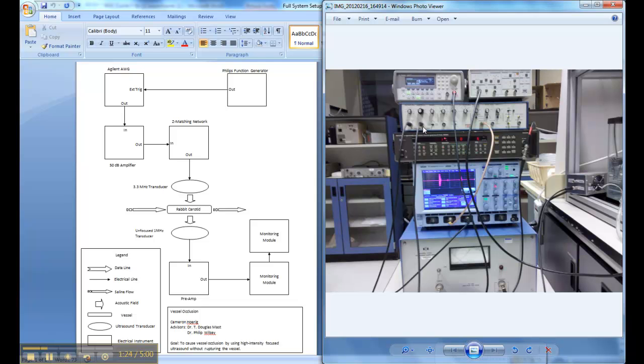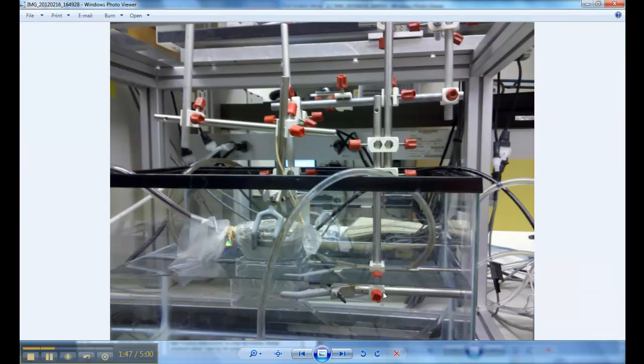So on the oscilloscope you can see here, this would be a pulse echo. This initial bang here is the pulse and then it turns into listening. And then right here behind the cord you can see where there's a peak starting. That'd be about the focus of the transducer, so we want to move the transducer to where that peak maximizes. This would be in the vessel, or the transducer in the vessel itself.